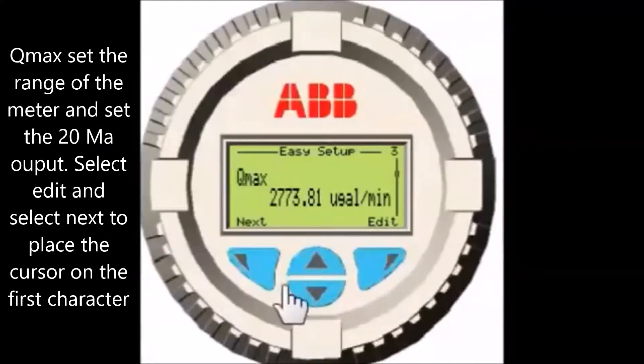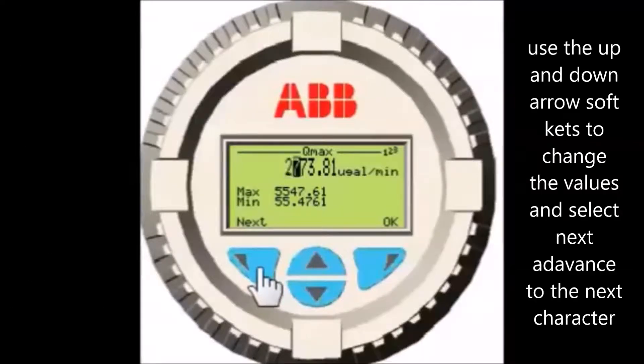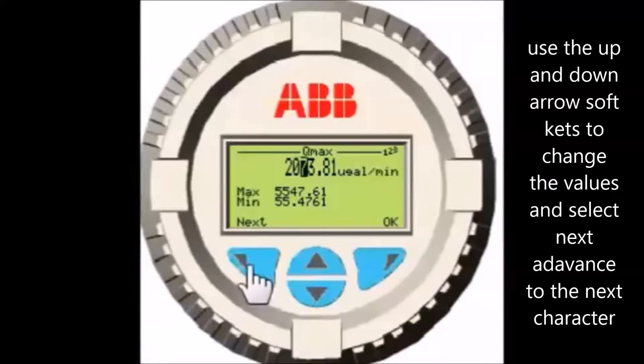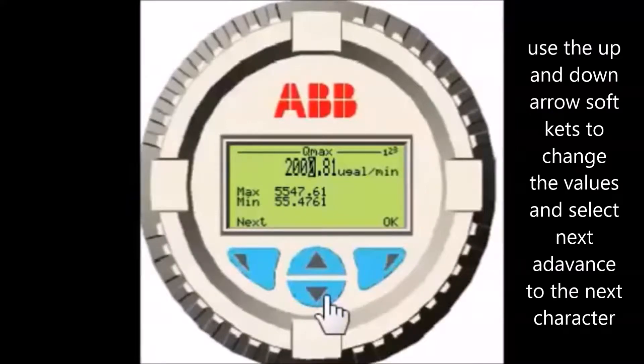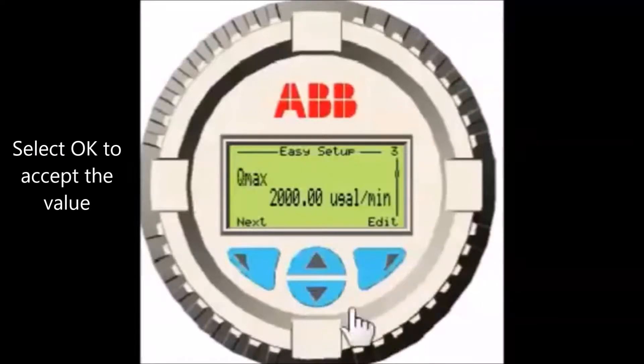Q max sets the range of the unit. This corresponds to the current output at 20 milliamp and also sets the range of all internal diagnostic messages and warnings. Select Edit — the current setting is displayed, and the maximum and minimum range for the flow tube is shown below; these cannot be exceeded. Select Next to place the cursor over the first character to be changed and use the up and down arrow soft keys to change the value. Repeat for all characters and select OK to accept the value.